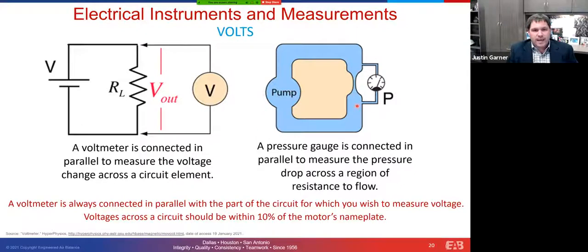So if you're looking across an orifice like we would have right here, you're going to get a pressure drop. Oftentimes we look at that in a water system to try and determine flow. It's kind of the same thing on the voltage side. You're looking for a voltage differential, and it's equivalent to the pressure in the system or the potential in the system. And it's interesting to note that you're always going to connect a voltmeter in parallel with either the ungrounded conductors in the system or between the ungrounded and the grounded conductor, if that's what you're looking for, because you're looking for voltage differential there.